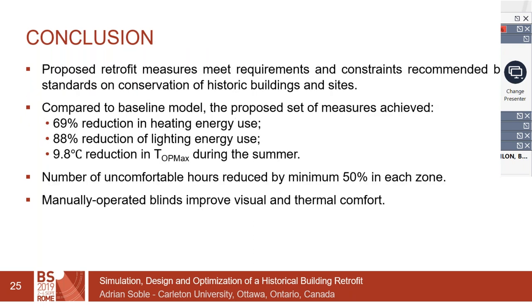In conclusion, the proposed retrofit measures meet the requirements and constraints recommended by the standards of conservation in the area. With our combination of optimized interventions, we achieved a 69% reduction in heating energy use, an 88% reduction in lighting energy use, a 9.8°C reduction in maximum operative temperature during summer, and a 50% reduction in uncomfortable hours in each zone. We believe manually operated blinds would further improve visual and thermal comfort.